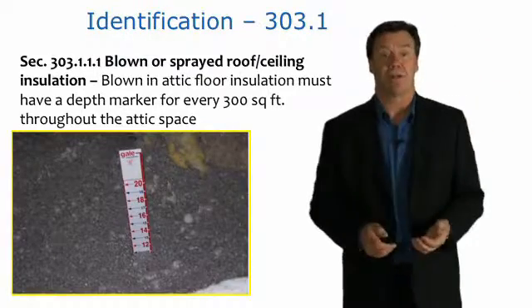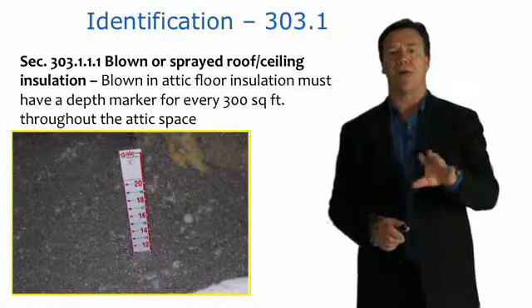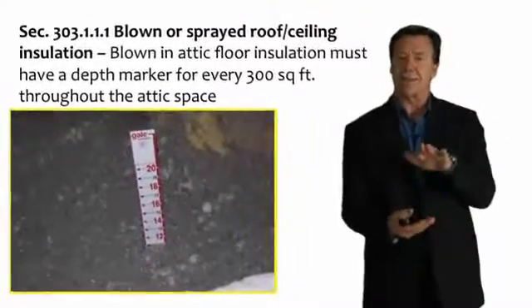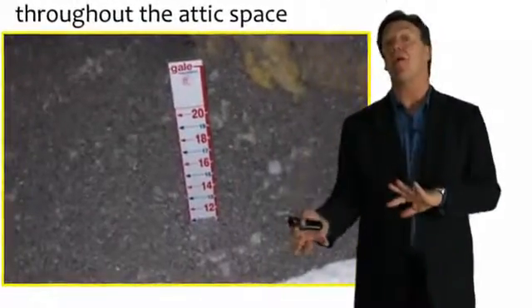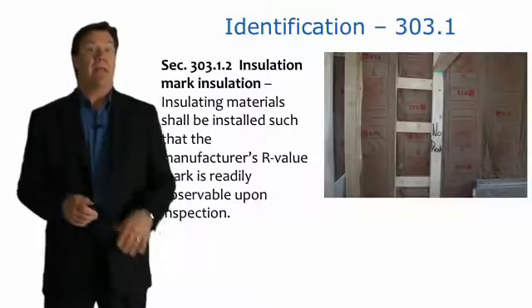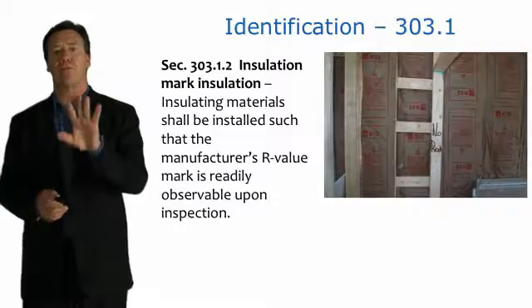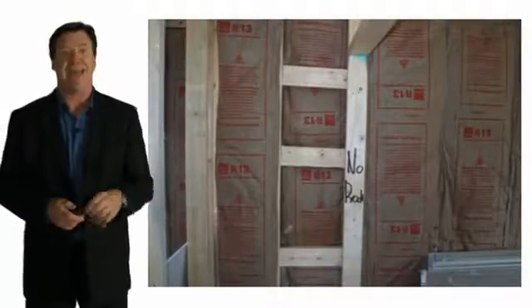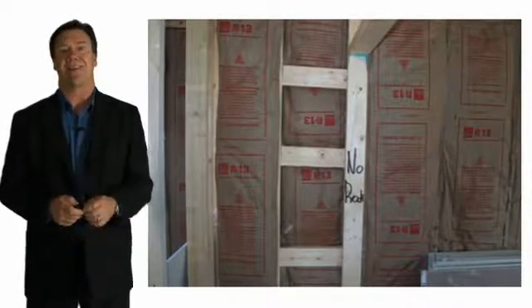With regard to blown insulation, not only do you have to have that certificate, but you also have to have a depth marker every 300 square feet throughout the attic space to make sure that the insulation is at its proper depth. The marker actually shows the inches and the R-value of the insulation right on it. Additionally, insulation materials themselves must be marked, so you can plainly read the manufacturer's R-value of that insulation.